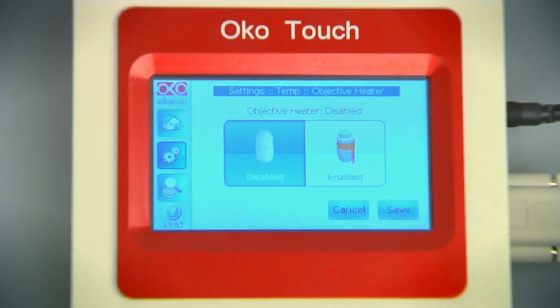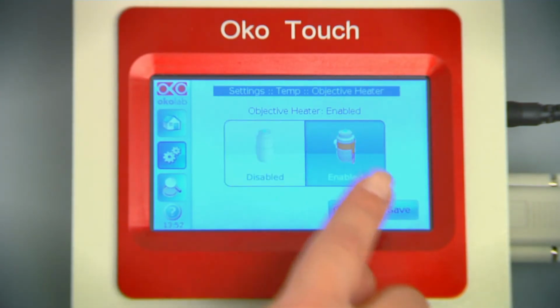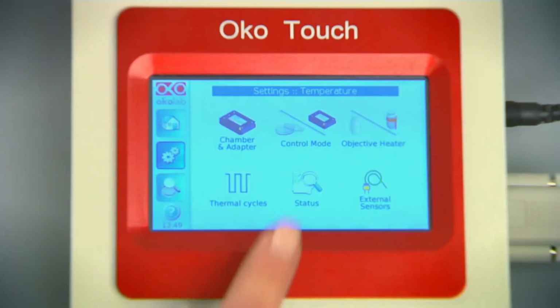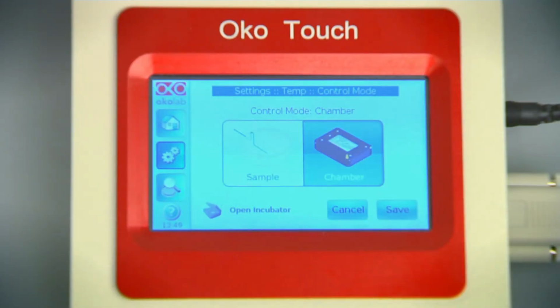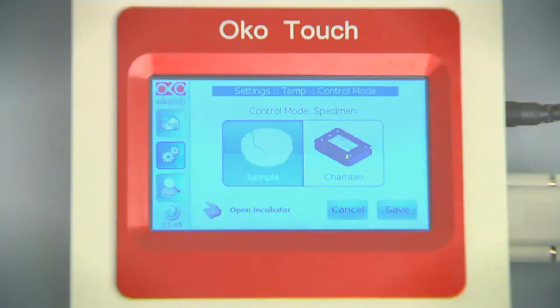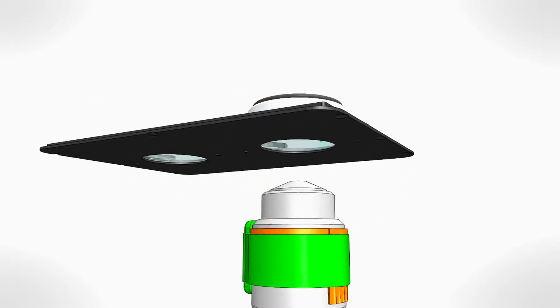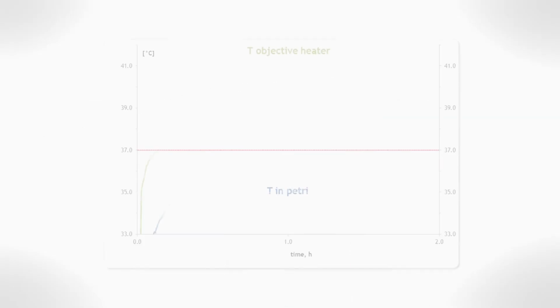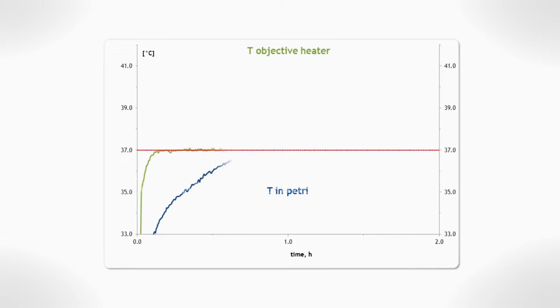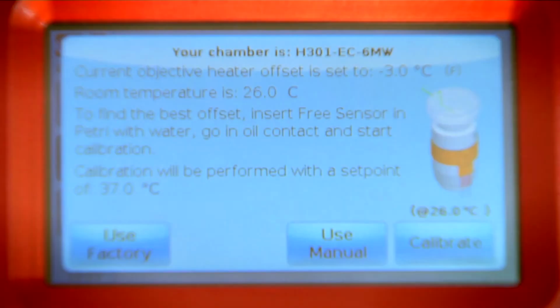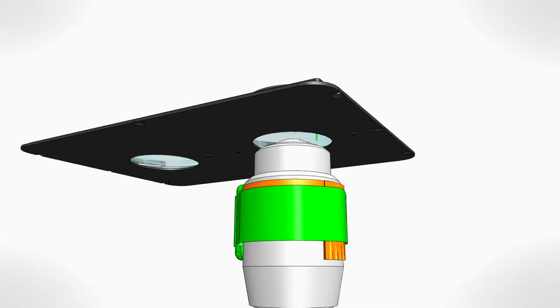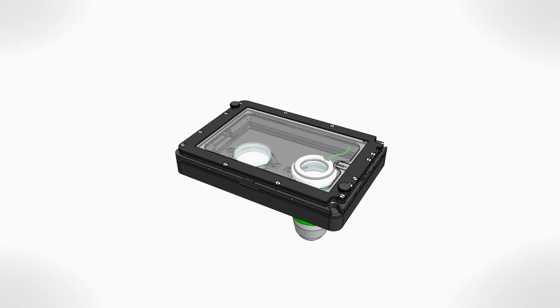Enable the objective heater from the touchpad and proceed to its calibration. Prior to starting the calibration, operate the incubator in sample feedback mode, keeping the objective not in oil contact. When the incubator has reached the desired set point temperature, start the calibration procedure from the touchpad and bring the objective in oil contact with the Petri containing the temperature sensor.